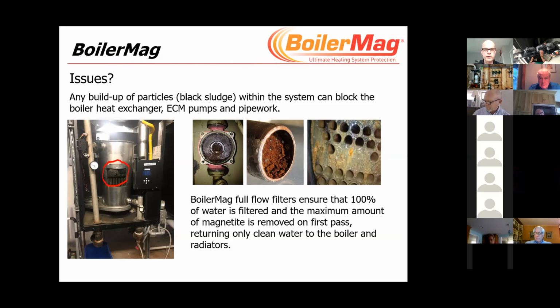The advent of the new combi boilers, the high efficiency boilers, the ECM pumps with the magnet inside, really means that contamination recirculating around old steel pipe systems can't be managed. The black sludge, or magnetite, or iron oxide as some people call it, starts to block up the heat exchangers. That magnet that drives the ECM pump becomes contaminated and won't turn anymore, or it tears the seals up, or we just get plugged heat exchanger bundles and pipe work.